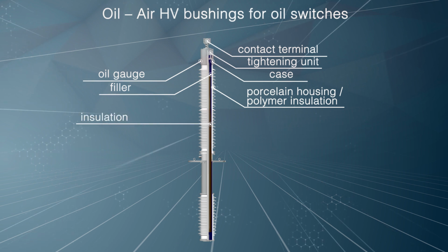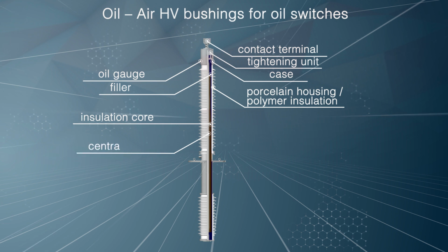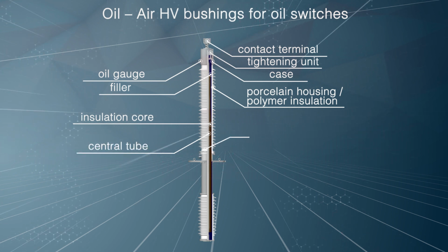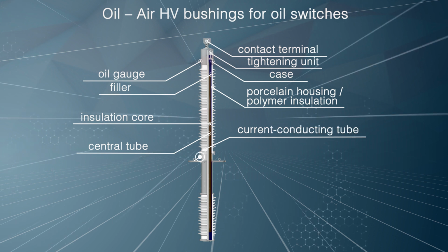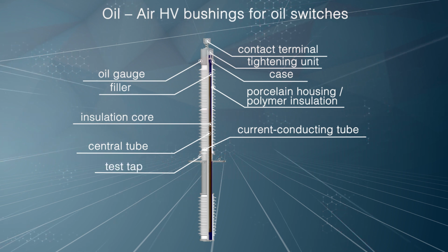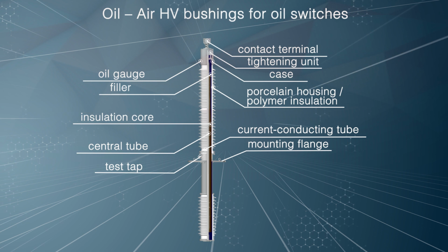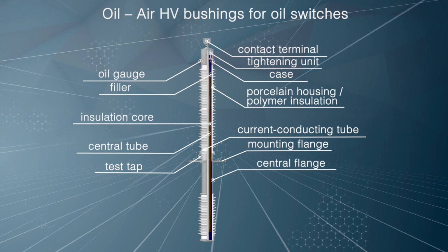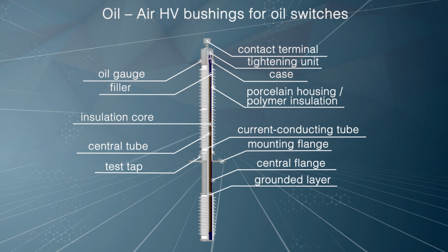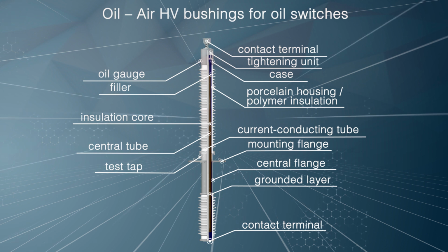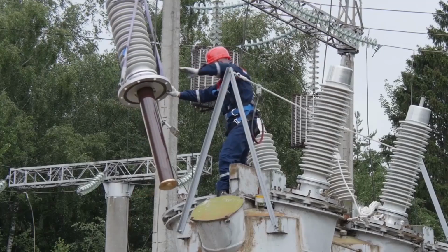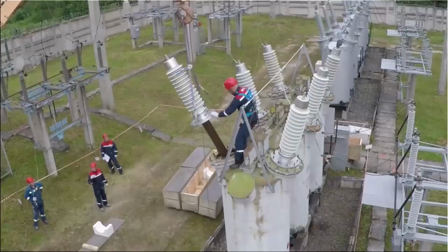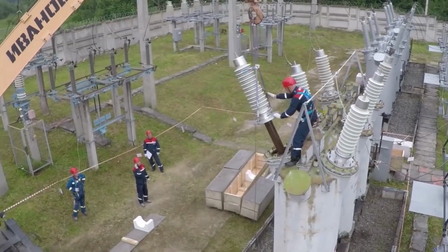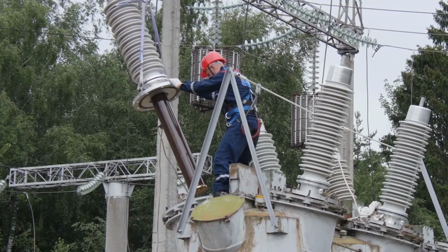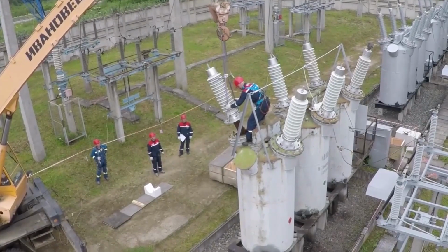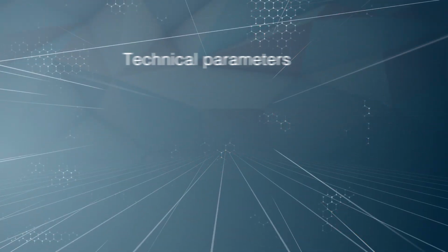The central tube for 110 and 220 kilovolt bushings and the rod for 35 kilovolt bushings are used for winding the internal insulation. The top shield is applied in the bushing designs with polymer external insulation and is used for equalizing the external electric field in the top part of the bushing. With the bushings using a porcelain housing, the case performs the function of the top shield. The polymer external insulation is used as an alternative to porcelain insulation on 110 and 35 kilovolt bushings. Connection to the circuit breaker. The type of connection of 35 kilovolt bushings depends on the type of the circuit breaker which they are installed on. Connection of 110 and 220 kilovolt bushings is done with the help of a contact tip screwed on the central current conducting element of the bushing.